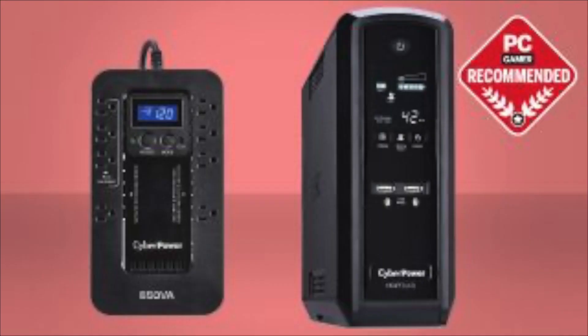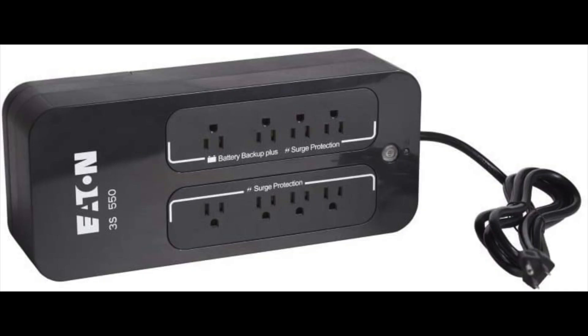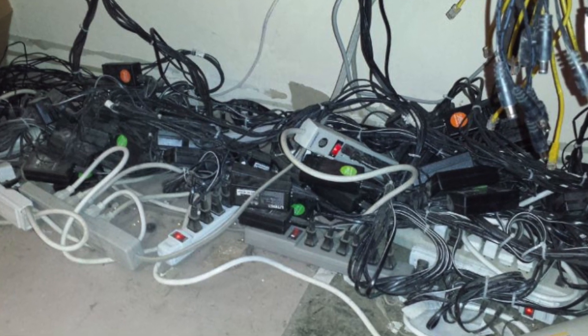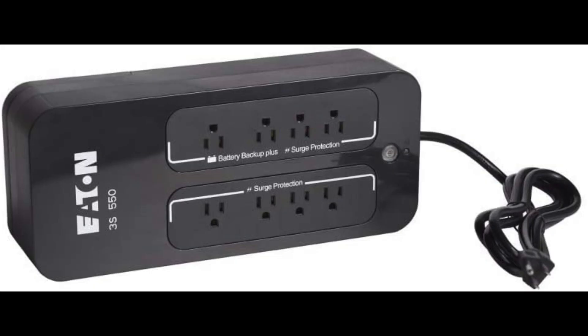As I learned in February during the Texas deep freeze, some UPSs cannot handle 65 Hertz and will not charge, meaning they will continue to beep until dead even though there is power to the outlet. There are some UPSs that can handle a wide range of Hertz, but the three I had could not. That meant we had to unplug everything from the UPS and plug it into the wall outlet. I've since replaced all of them with UPSs that can handle 70 Hertz.